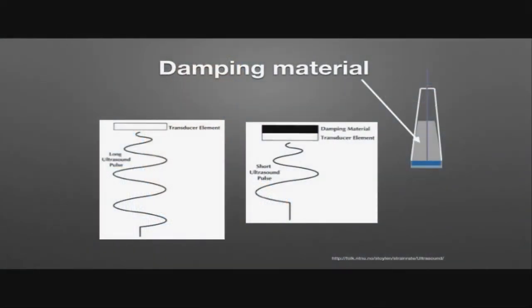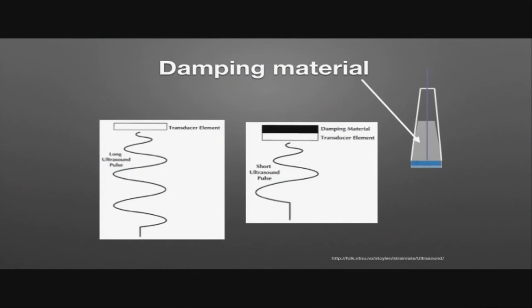The damping material also helps prevent sound waves being reflected back from the face, reducing interference. The negative side is that it also reduces the intensity somewhat, so amplitude is not quite as great once the pulse duration is dampened. We can see that adding damping material reduces the pulse length and improves resolution, but reducing pulse length also increases bandwidth — the range of frequencies within that pulse. Since transducers have a limited bandwidth, there's a tradeoff between resolution and bandwidth limitation.